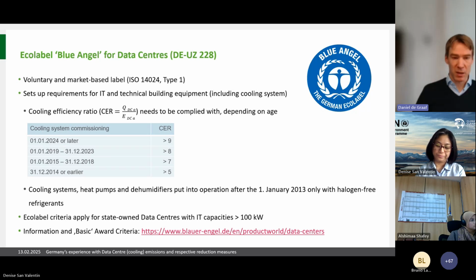For the cooling system, there is the cooling efficiency ratio, which was already introduced by Bruno. This is calculated by the heat dissipated to the ambient, divided by the energy the cooling system needs to do that. This cooling efficiency ratio needs to be greater than 9 - a quite ambitious value for new data centers commissioned in January 2024 or later - and it goes down to a CER value greater than 5 for older data centers commissioned in December 2014 or earlier.